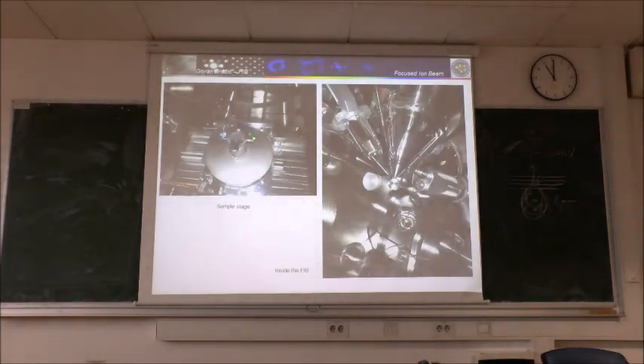You can put 5 samples inside, 1, 2, 3, 4, 5, also the middle. It's a very huge stage, chamber. And this is the image from part of the sample. This is the electron column, ion column, one detector, another detector, a third. This is the EDS system. And you can imagine a lot of very tiny systems for gas injection, and micromanipulators should be somewhere like here. Those things are moving in and out. And it's very easy to destroy this inner part of the FIB relatively quickly. It could be quite expensive and so on.